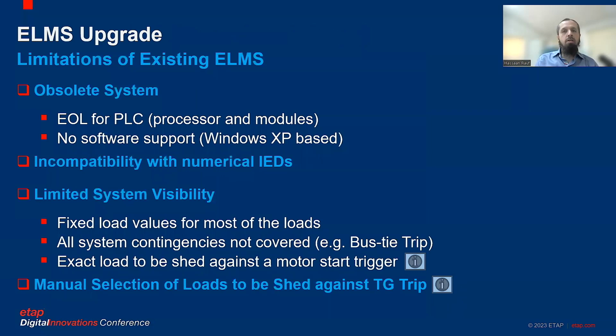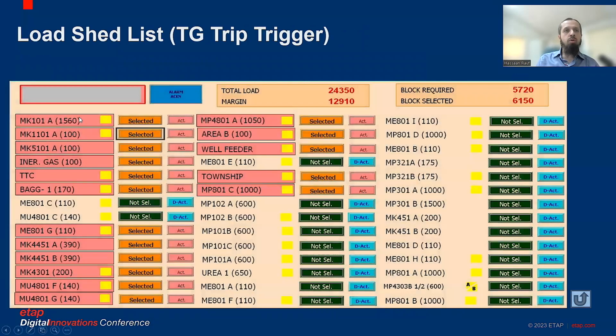Another limitation in the existing system was that the selection of loads to be shed against the TG trip trigger was manual. Again, a screenshot from the old system is shown. This is the sacrificial load list, and the system during runtime calculates, based on the feeder status, the system load and the capacity of the generation, the requirement of load shedding. You can see the value in the block required shed. Based on this, the operator would then manually select each of the loads he wants to be shed against this TG trip trigger, to match these two values. Again, because this was operator dependent, it has certain limitations.